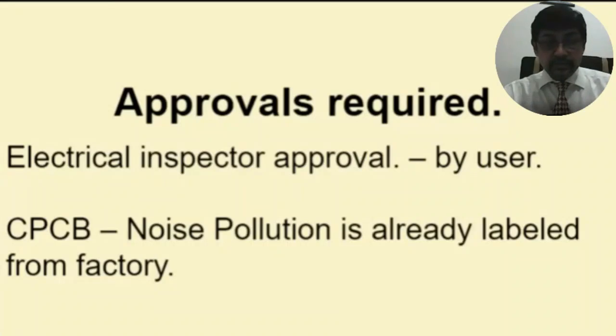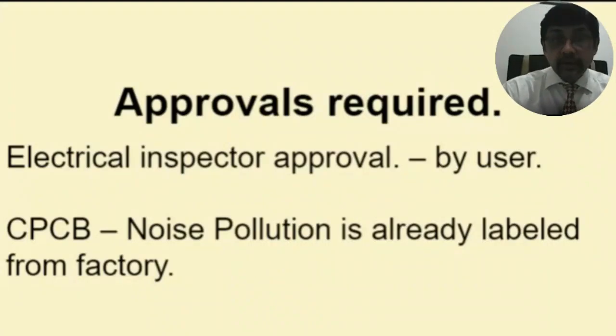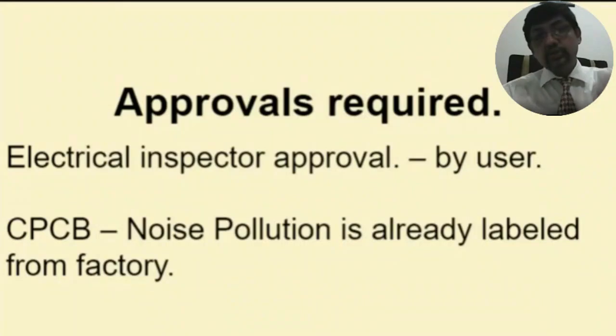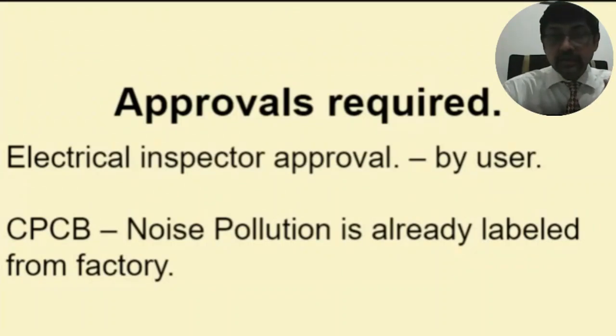Of course, the electrical inspector also checks that the earthing is properly done, because each generator requires four earthings, I told you. Two are for neutral and two are for body. So these are the four things, and a proper isolation between the mains and the DG set is done. In case it is not an automatic panel, then a manual changeover switch is installed there. So they will see that either an automatic changeover or a manual changeover is installed, and the earthings are done properly. So that's the job of an electrical inspector.